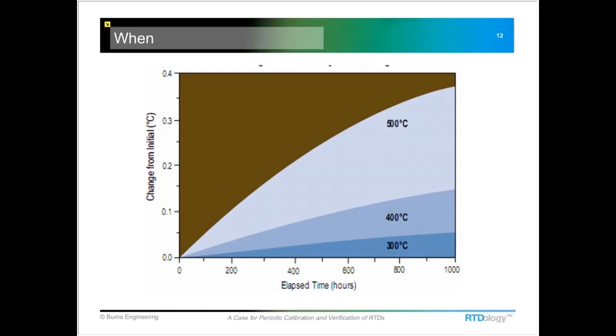So this graph shows some typical drift numbers for an RTD. As you can see, up at 500 degrees C, if we run for 1,000 hours, we could possibly end up having 0.35 degrees C of change just due to drift. These are worst case numbers, but it gives you an idea that when the temperature ratchets up, you can have more drift, and you're going to need to take that into account in your calibration frequency. Down below 300 degrees C, it's a very small number. Most pharmaceutical or food and beverage processes are going to be less than 200 C, and there the drift is almost nothing, but over a long period of time there still can be just a little bit happening.